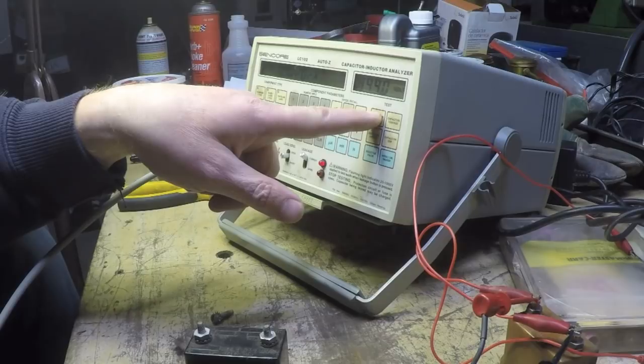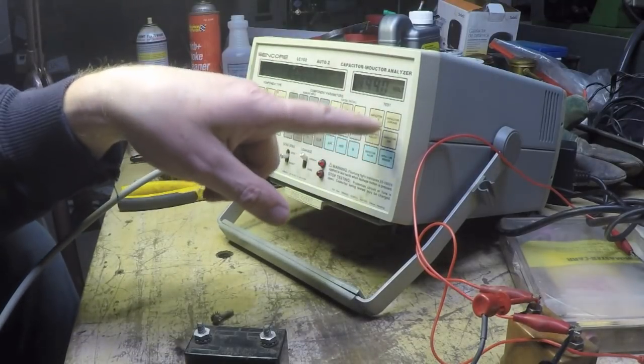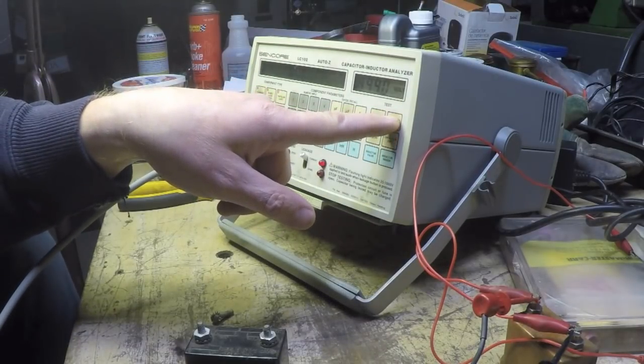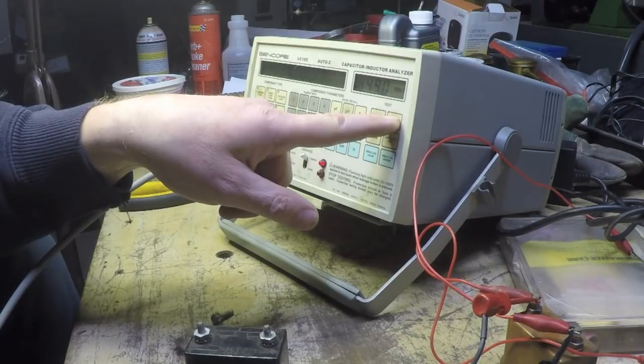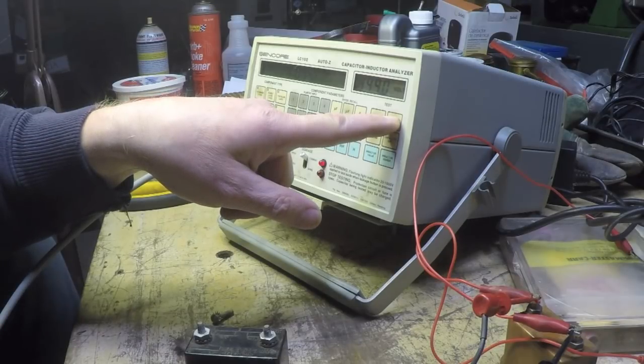Verified the value, 0.002, and if I do a leakage test on these caps at 999 volts, they still pass with flying colors. They're actually showing 0 microamps of leakage current.